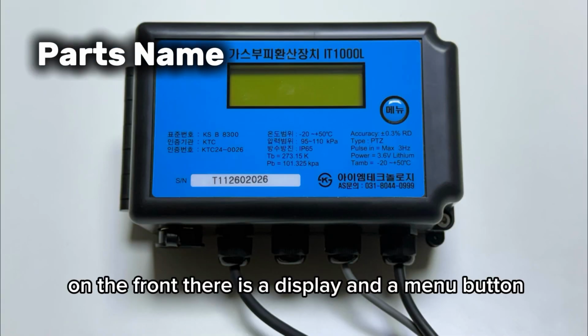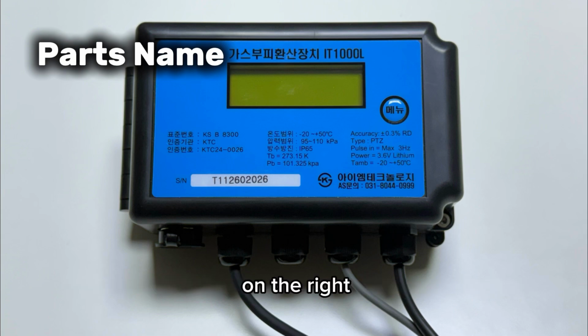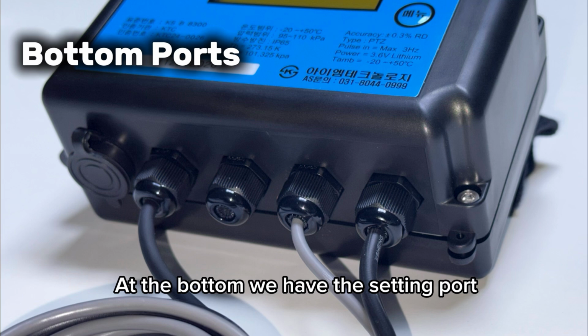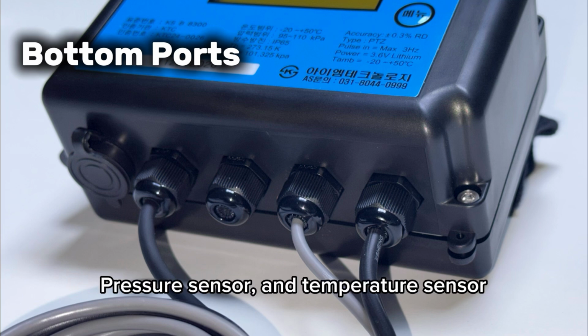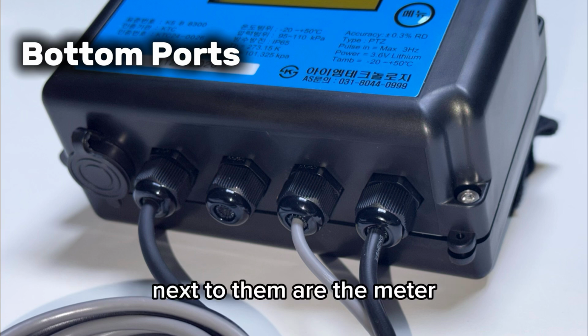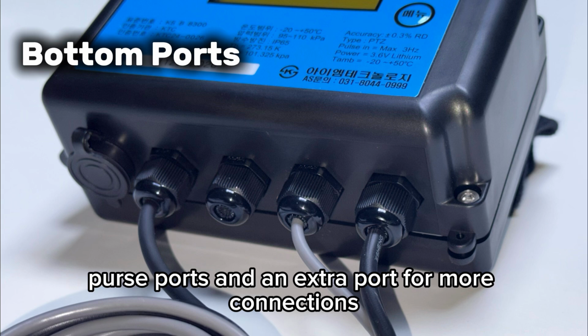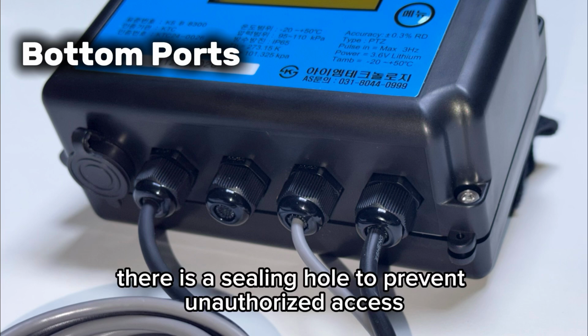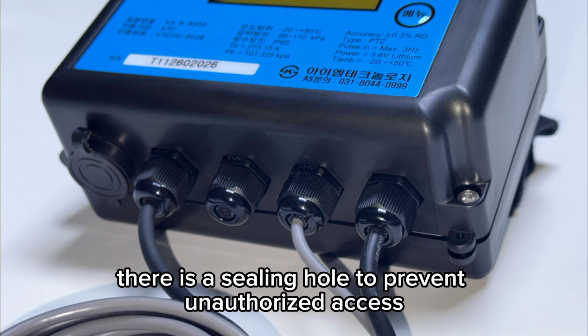On the front, there is a display and a menu button on the right. At the bottom, we have the setting port, pressure sensor, and temperature sensor. Next to them are the meter pulse ports and an extra port for more connections. On the bottom right, there is a sealing hole to prevent unauthorized access.